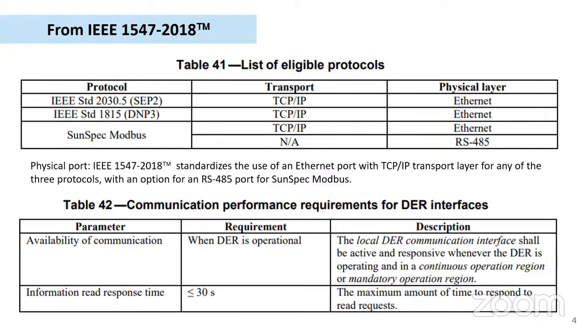So it's really about the utilities identifying what their system's going to be up to a site, and then I think the market will start driving those interface devices and the communications with different inverters, regardless of what's built into the inverter. We might have an inverter with a 2030.5 port, or you might have inverters with only SunSpec Modbus ports. And a power plant controller might have the 2030.5 port.